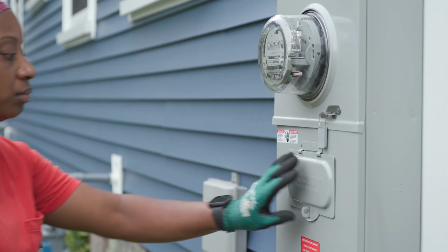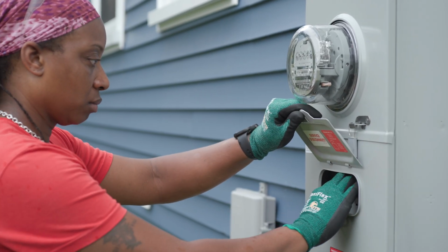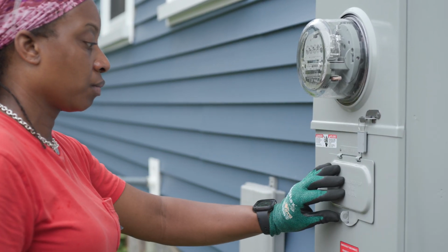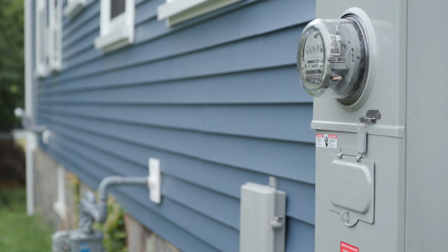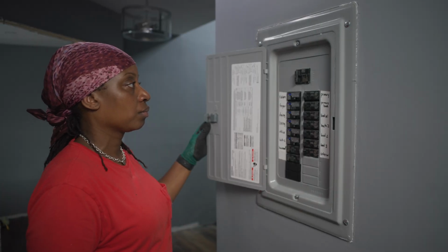If you're considering updating a standard breaker to an AFCI breaker, you should hire a licensed electrician, or check your local building codes to see if this is a project that a homeowner is allowed to do. It's safe to install AFCI breakers on circuits that have GFCI receptacles, such as those installed in bathrooms or a kitchen. Before you start, be sure to shut off the main power to the main circuit, cutting power to the entire house, so you may need a battery-powered light on hand.